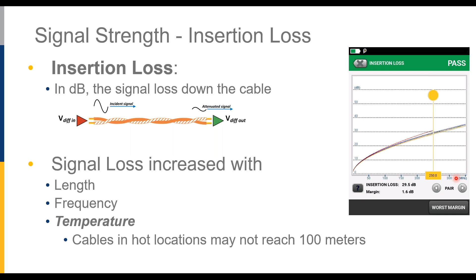You may not be able to go 100 meters. That 100 meters is contemplated on a room temperature cabling, 68 degrees Fahrenheit. And as you get to higher temperatures, you'll see that we need to derate or reduce the length of the cabling to compensate for the additional insertion loss that's going to be introduced there.